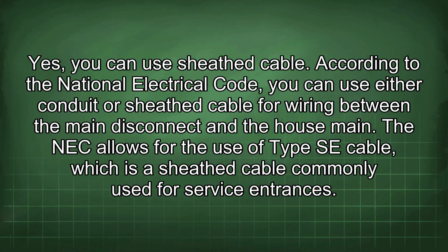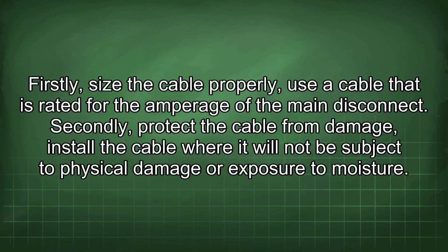Yes, you can use sheathed cable. According to the National Electrical Code, you can use either conduit or sheathed cable for wiring between the main disconnect and the house main. The NEC allows for the use of Type SE cable, which is a sheathed cable commonly used for service entrances. Firstly, size the cable properly.